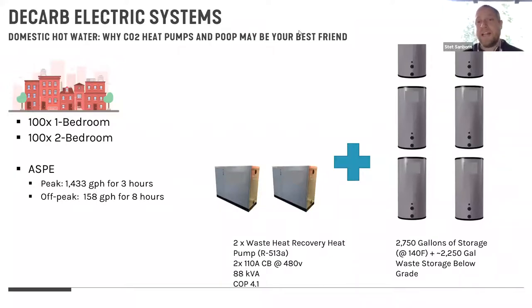And the reason why is because of that low connected load, that 88 kVA for this building. I might be able to pick up that 88 kVA through efficiency measures in the building, reducing other loads, you know, a lighting retrofit, glazing improvements to reduce AC load. I can probably pick that up through other efficiency measures and reducing the size of those systems so that I can have a net neutral impact on my electrical gear.